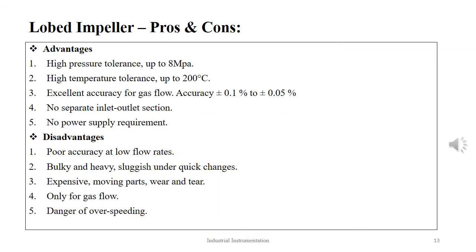The advantages of the lobed impeller are: very high pressure tolerance up to 8 MPa, very high temperature tolerance up to 200 degrees Celsius, excellent accuracy for gas flow about 0.1 to 0.05%, no separate inlet-outlet section, and no power is required for running this device.